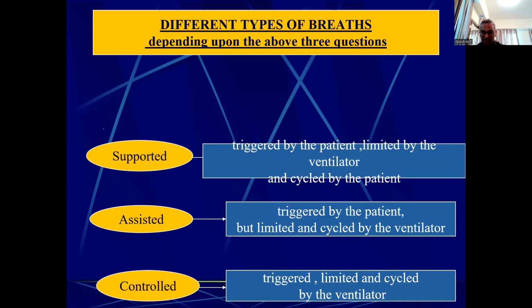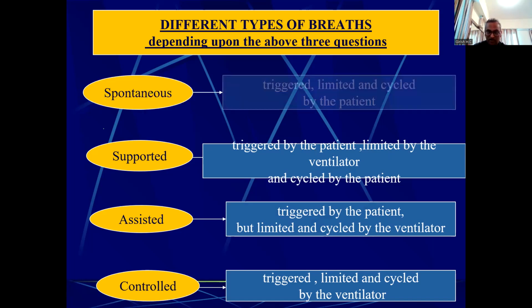So in controlled breath, everything is done by the machine. In assisted breath, one thing is done by the patient, other two are done by the machine. Supported breath, only one thing is done by the machine, which is giving a certain amount of pressure, but both triggering and cycling is done by the patient, right? And if you go one step further, that's what we are all doing right now. We trigger, we limit, we cycle our breaths by ourselves.